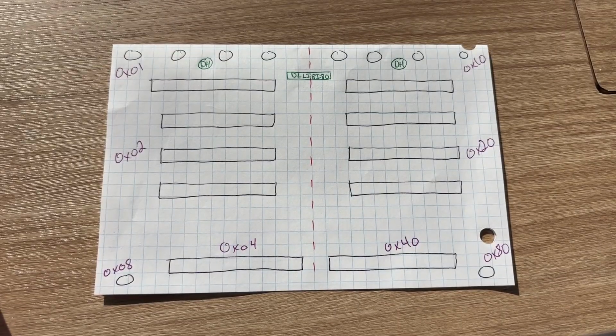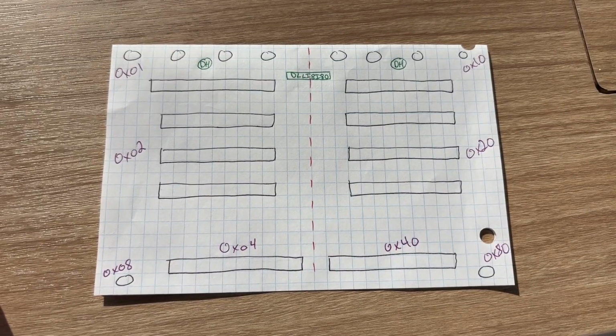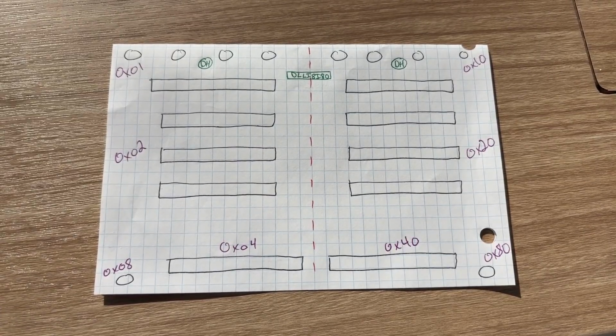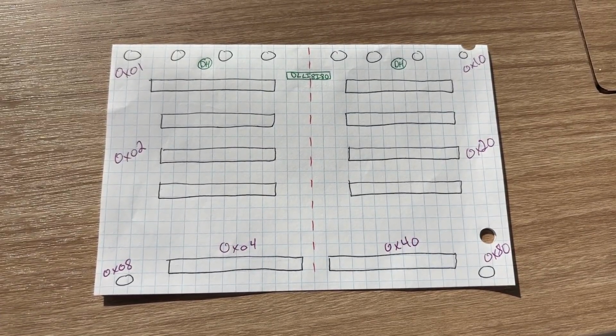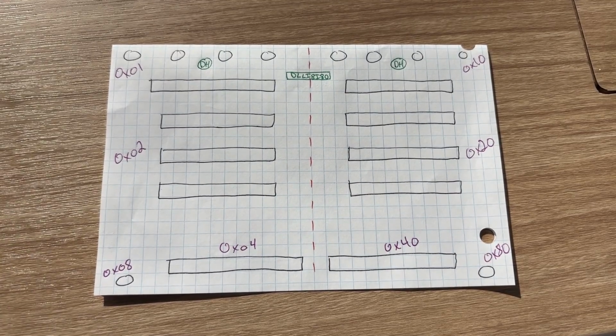However, because this training room has partitions and daylighting, it poses a particular programming problem. So the challenge is that I have to control each area separately and combined, and daylight regulate each space separately and combined, all while integrating with the building management system using BACnet. We can go about this in one of two ways.